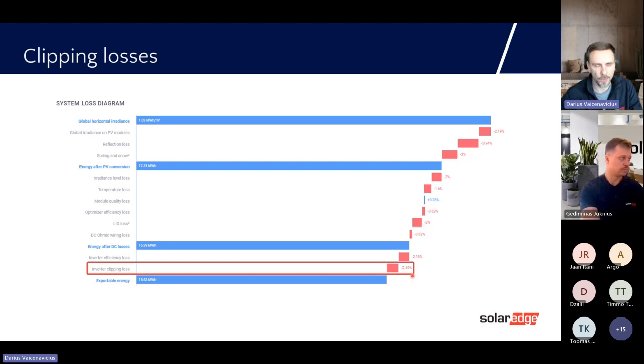We had a 5 kW project size, and initially they went with inverter undersizing. Of course, we did 1-to-1 on the STC values, but since it was an East-West system, the orientation was not perfect. The actual undersizing was around 80%. And when we started to look at how to save money, we had long discussions about what cables we should choose for the AC side. Because as we already know, if it's undersized to 80%, the inverters will never reach 100% of AC power. So maybe it's possible to use thinner cables and smaller circuit breakers.